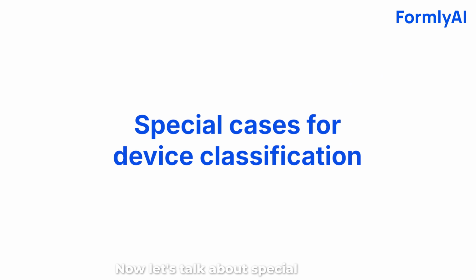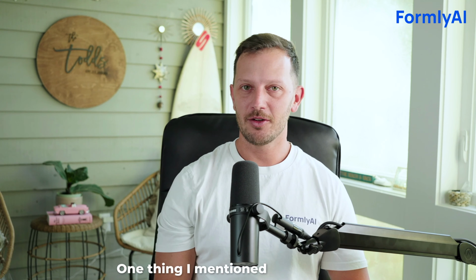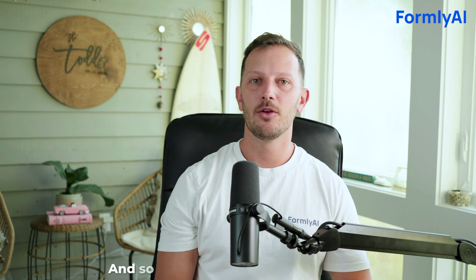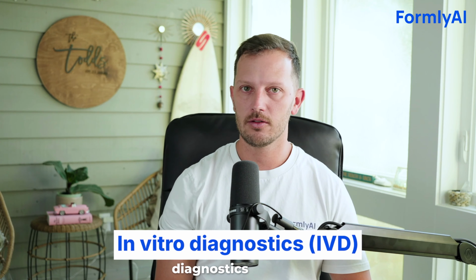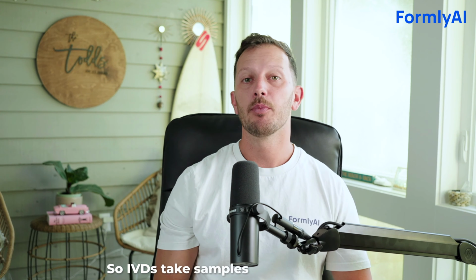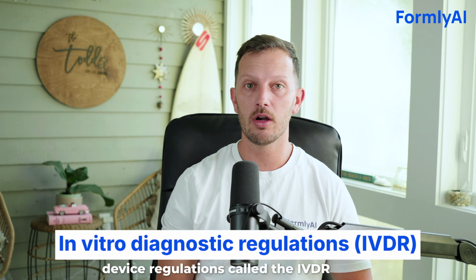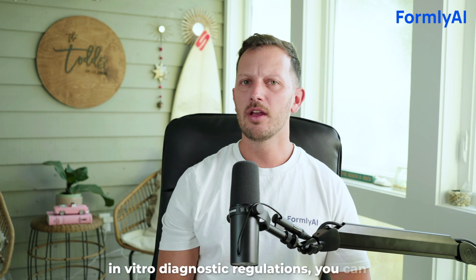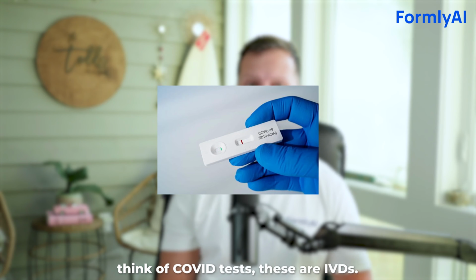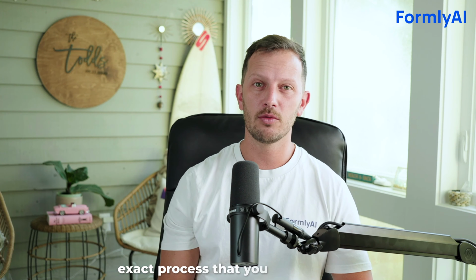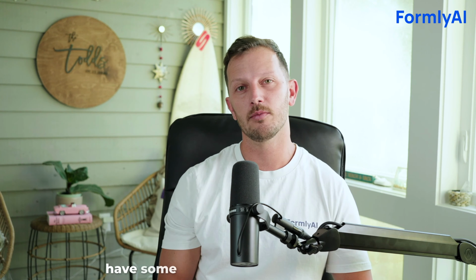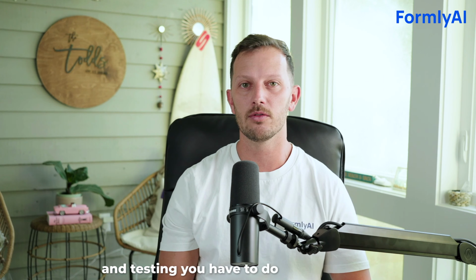Now let's talk about special cases for device classification. One thing I mentioned earlier was in vitro examinations, and these devices are called in vitro diagnostics, or IVDs. IVDs take samples from the blood or urine outside of the body, and they examine and analyze them there. They are slightly different than your traditional medical devices, and they're actually governed under different device regulations called the IVDR, or the in vitro diagnostic regulations. You can think of COVID tests. These are IVDs, and they go through the same exact process that you would with a traditional medical device, but they have some slightly different documents and testing you have to do for safety and performance.